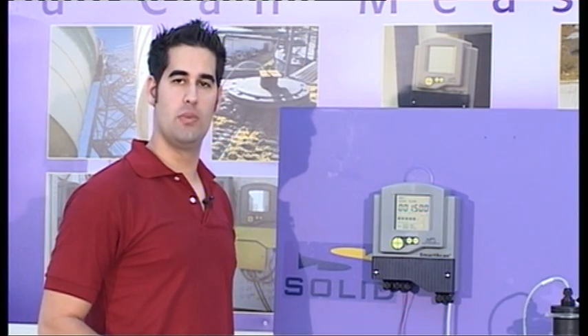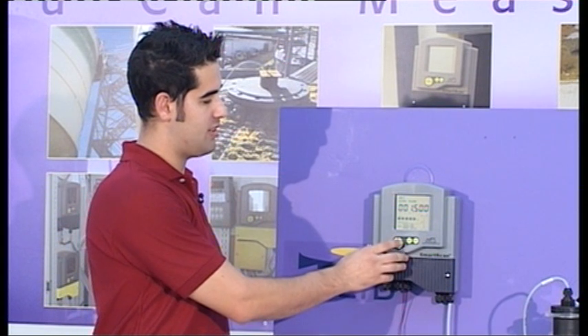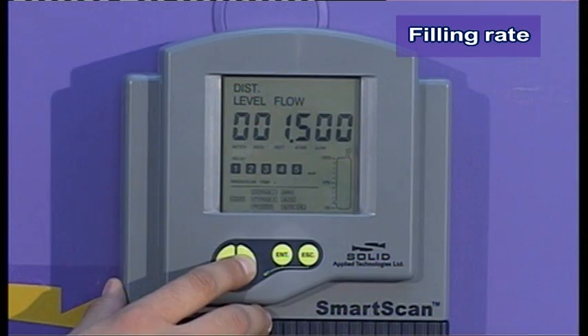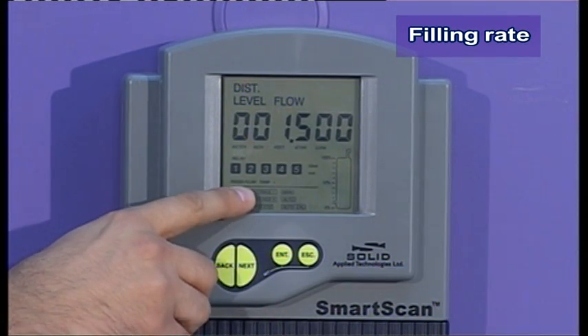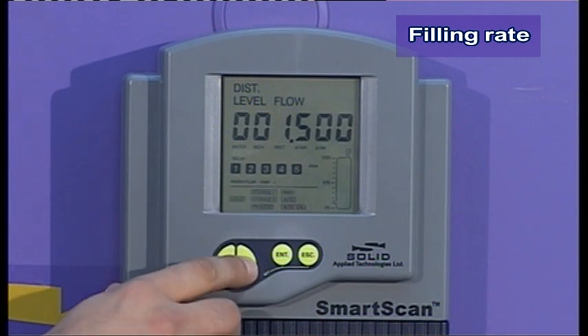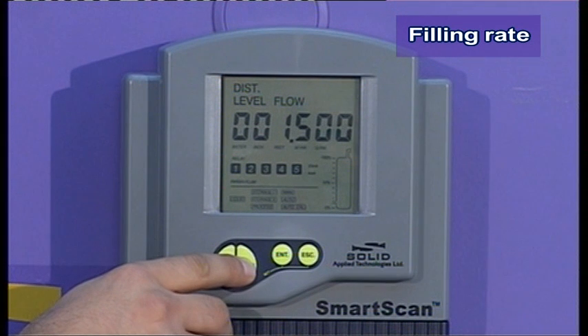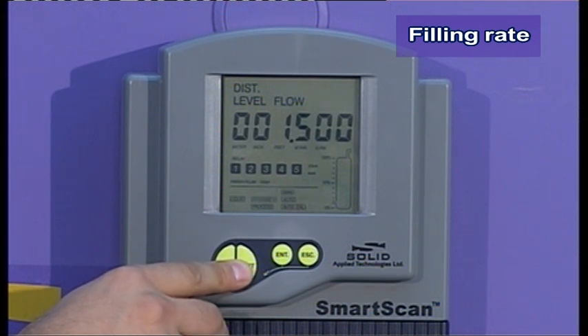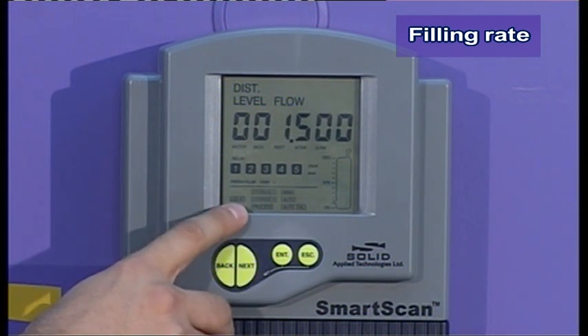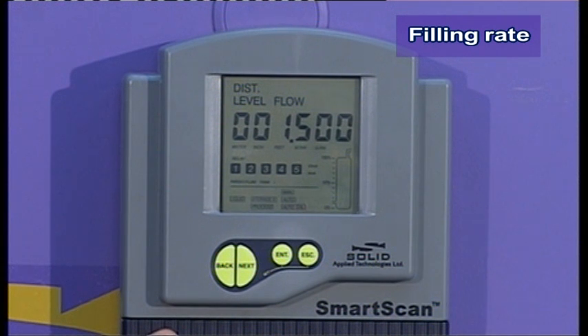After setting the 20 milliamps value, we will set the filling rate. Filling rate section is below the tank height. We have three types of filling rate. Storage 1, which indicates 20 centimeters per minute.